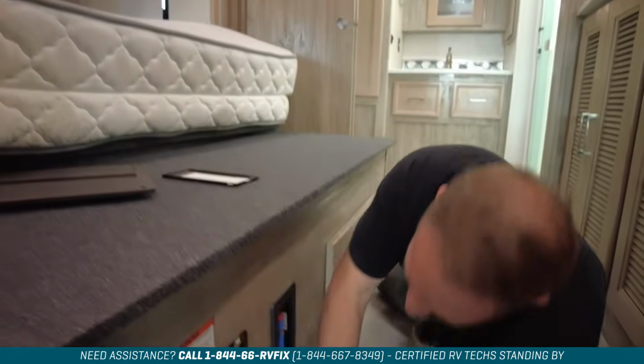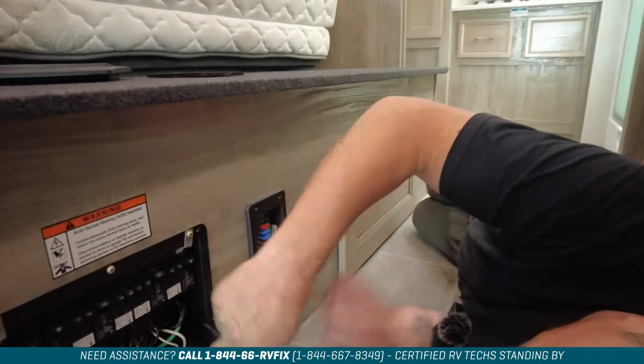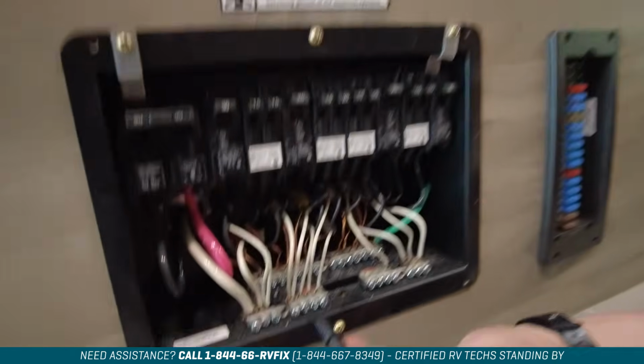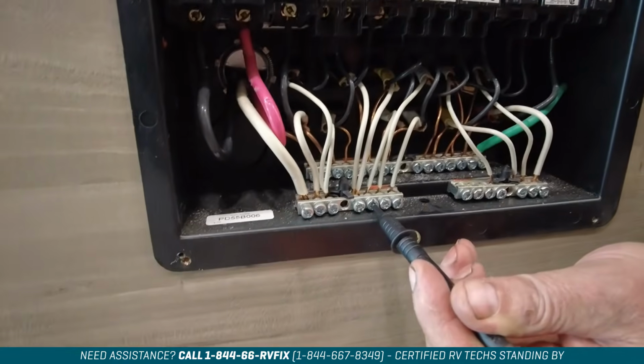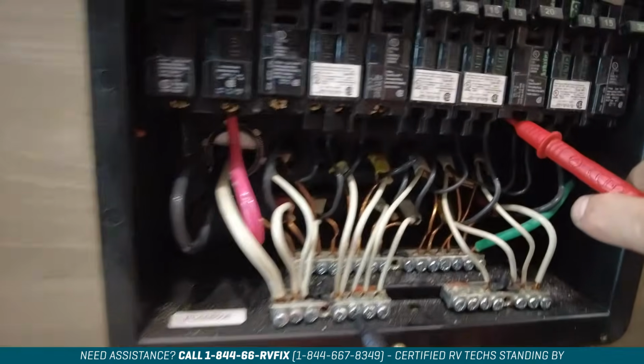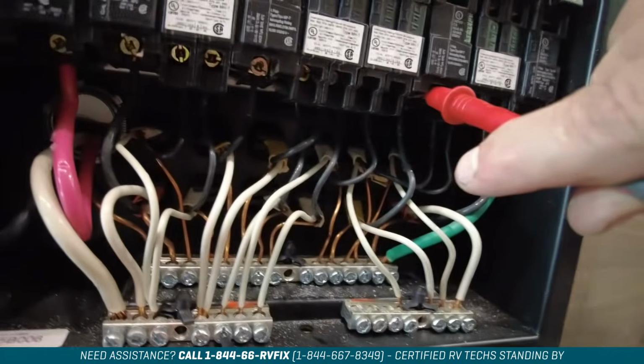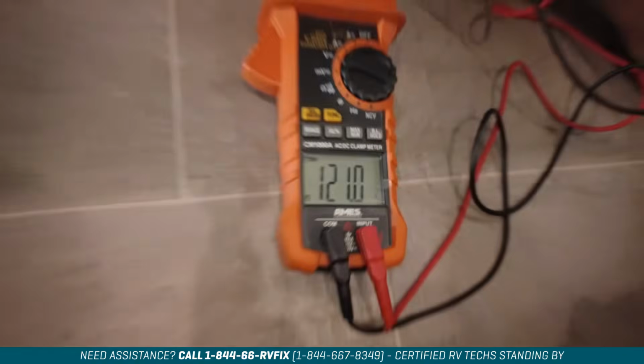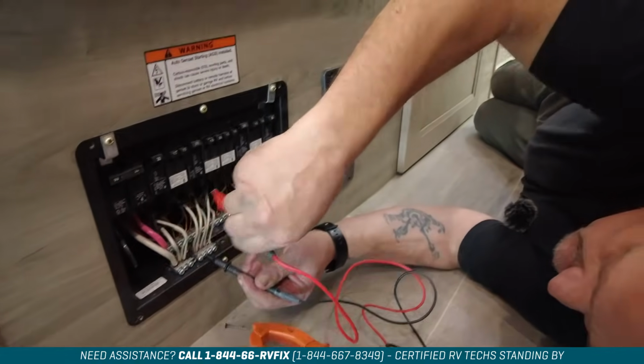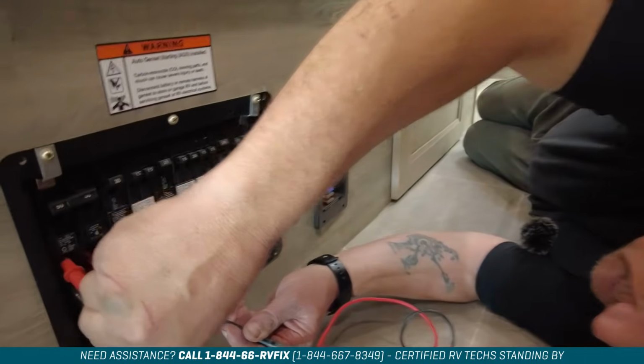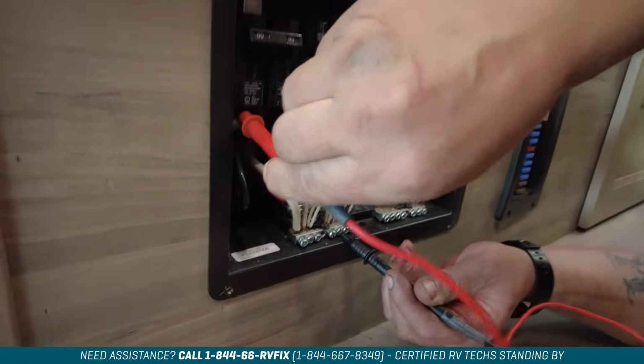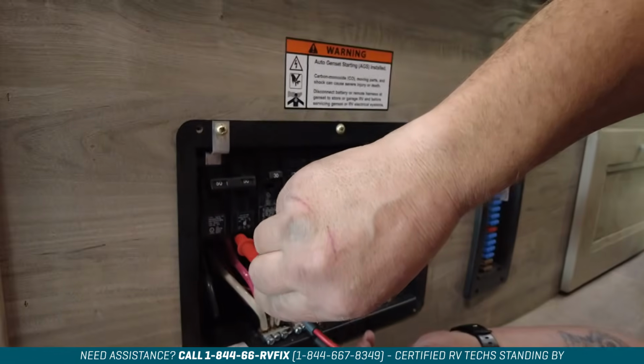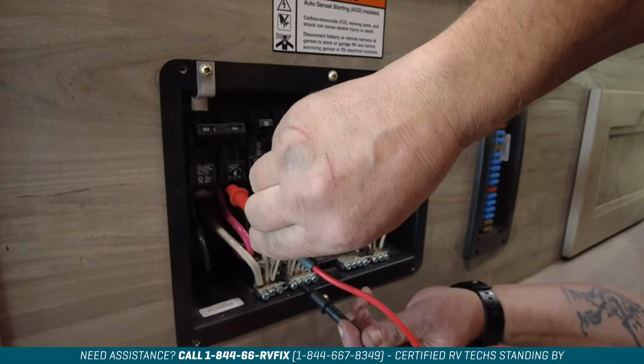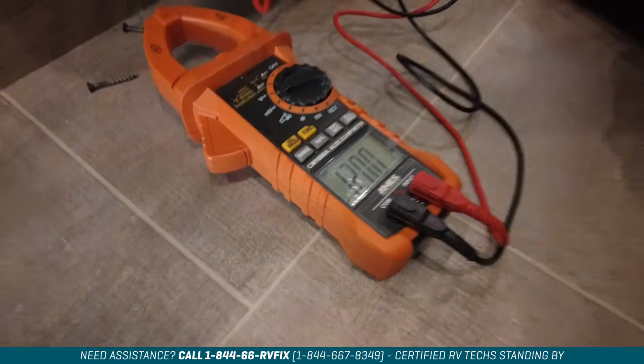Now I'm going to get down here a little closer. I can put my black probe on the neutral bus, where all the white wires are, and touch the red probe to the screws on the breakers, and I can see I have 120 volts coming in. On this particular coach, it's a 50 amp coach, so I've got a black line coming in from my shore cord with 120 volts, and a red line coming in with 120 volts as well. We definitely have power coming in.